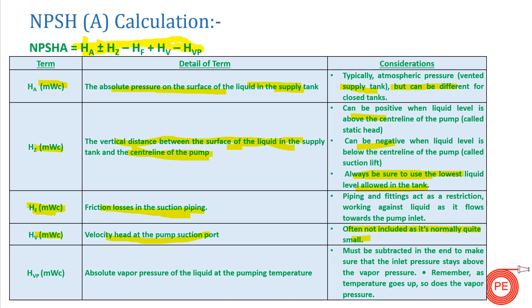The next and most important term is minus HVP — the absolute vapor pressure of the liquid at the pumping temperature. When HVP comes into picture, we know that if the pressure of water falls below its vapor pressure, the water starts boiling. If a pump is pumping water at 20°C, the vapor pressure will be different than if it is pumping water at 100°C, because HVP is a subtracting term from the other values.